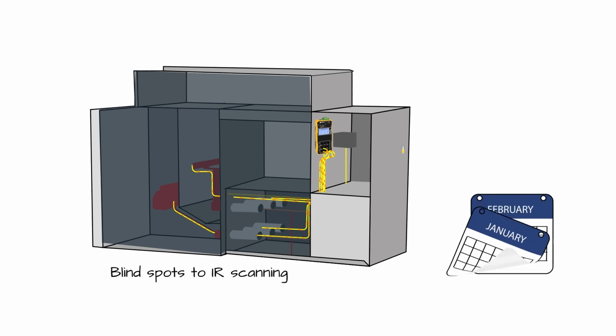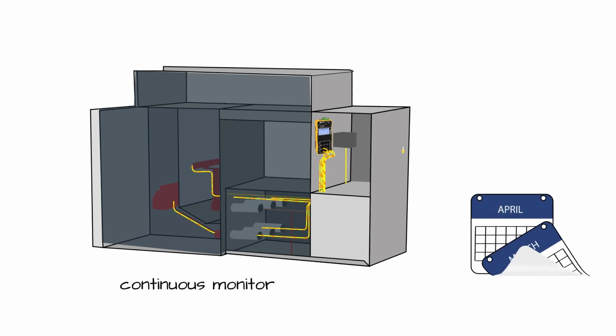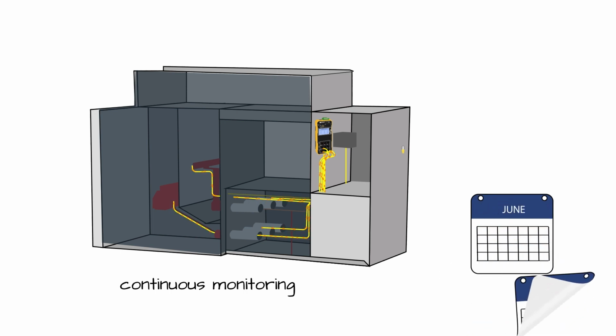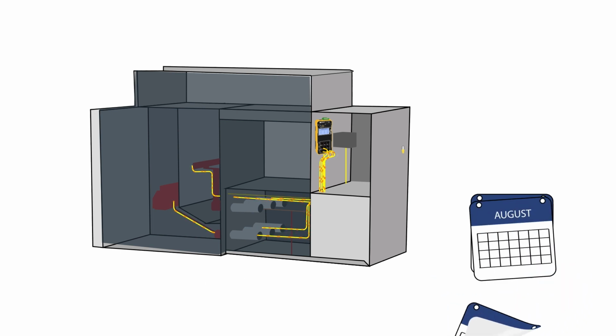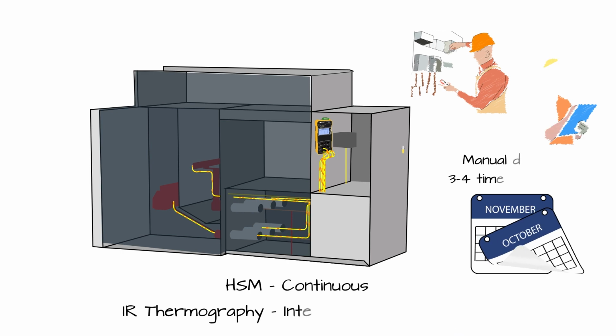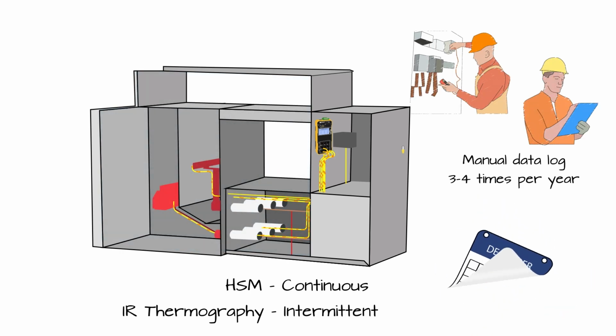The most obvious benefits of the HSM over IR thermography come from the continuous real-time monitoring feature. In addition, the successfully proven measurement accuracy of the probes is not subject to calibration errors, as can be the case with IR scans.